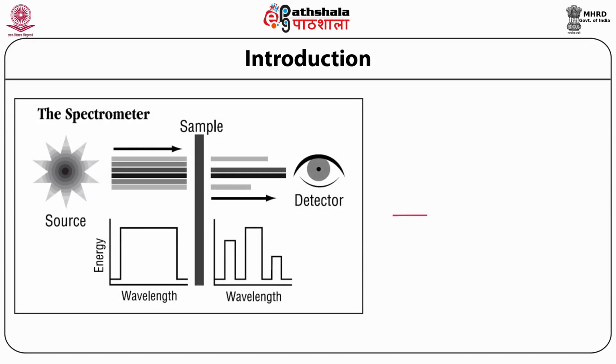In the normal instrument process, as shown in the figure, the source infrared energy is emitted from a glowing black body source. This beam passes through an aperture which controls the amount of energy presented to the sample and ultimately to the detector. And we will talk about the interferometer. The beam enters the interferometer where the spectral encoding takes place. The resulting interferogram signal then exits the interferometer.